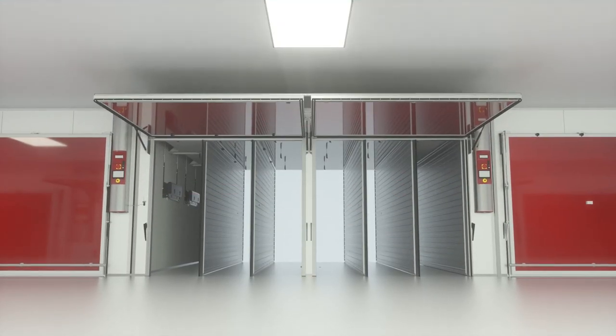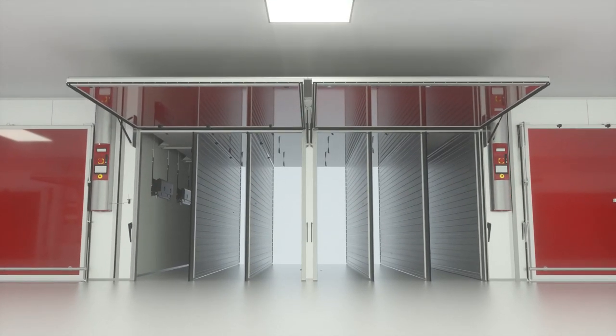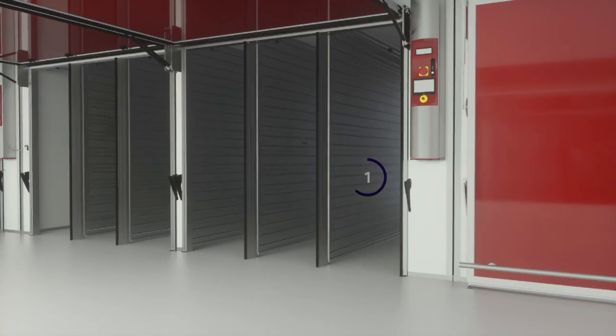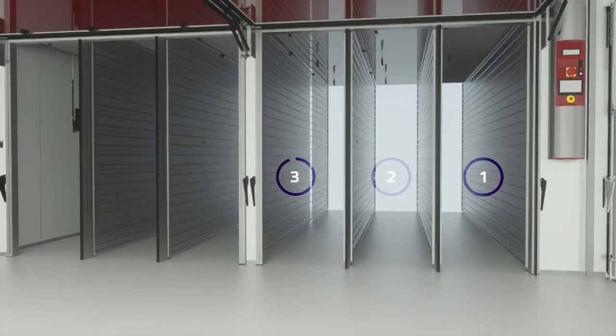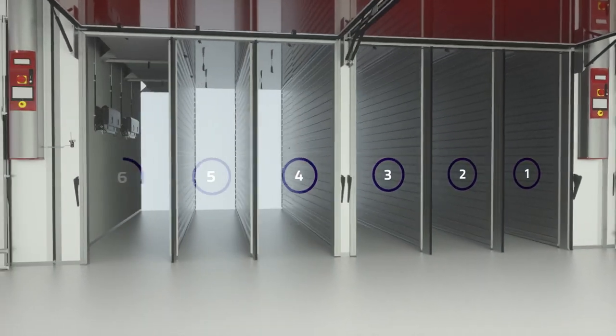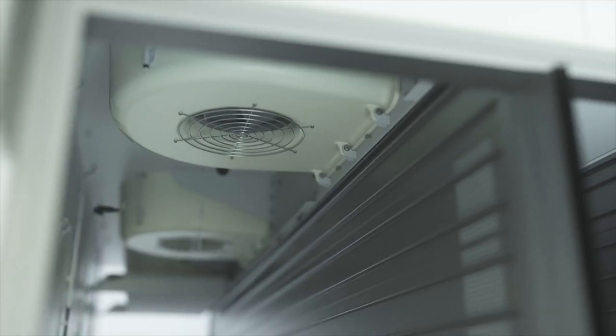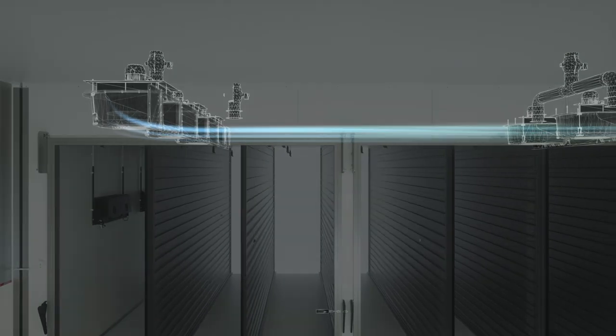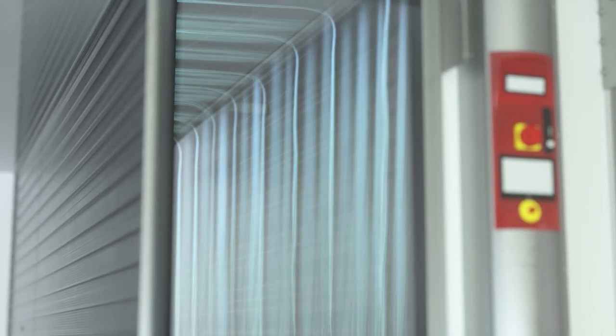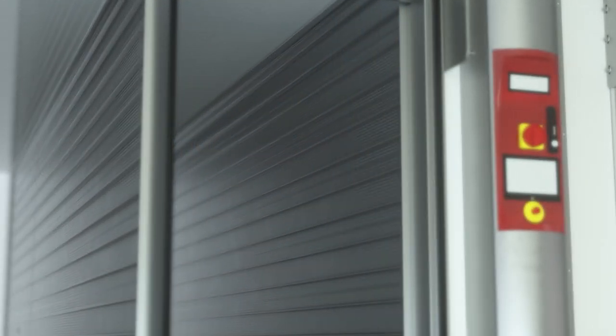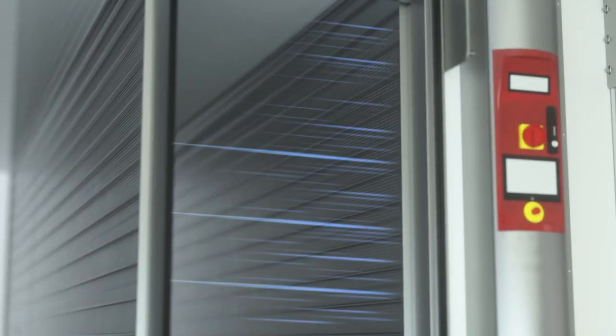We've created microclimates by dividing the incubator into six sections using radiators that contain small openings for air to move through. To start with, air is blown over the false ceiling. The air then ends up in a side chamber where air pressure is built up. Air will always follow the way of least resistance and will therefore leave the side chamber through the openings in the radiator.